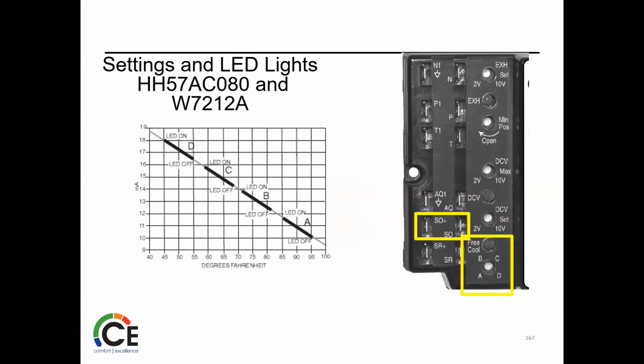That one throws folks off a bit, the ABCD selection. Again, it's just a matter of temperature, right? When do you want free cooling to activate? So obviously D is the setting that we use most in our area, which gives you that 45 to 55. So if the temperature is below that, that's when free cooling is going to operate. And then again, if you're not getting that, then we have to go back to our thermistor, because that's where it's getting its input from. Maybe your thermistor's off, or maybe it fell down, or got some debris on it, who knows? But that's a big part of it.